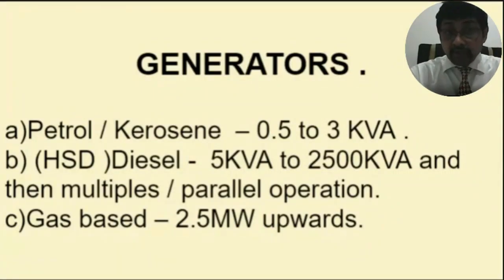But we have HSD, which is high-speed diesel. High-speed diesel generators are the most commonly used machines or standby supply in industry. 5 kVA to 2000 kVA is the range where these generators are popularly running, and they are so easy to use, handle and maintain that they have taken over all the other generators, which were initially with LDO, that is light diesel oil.